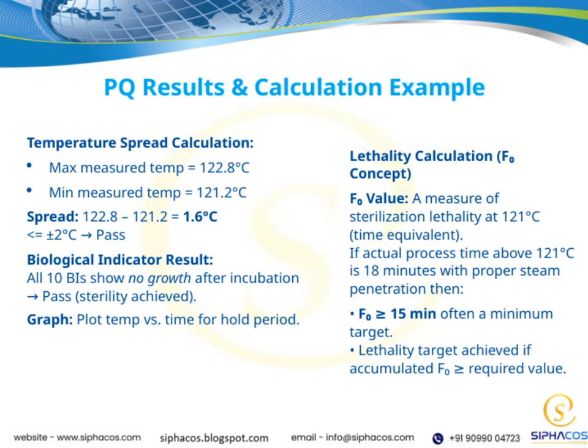Moving on to the PQ results and a calculation example, first, the temperature spread calculation. The maximum measured temperature was 122.8 degrees C, and the minimum was 121.2 degrees C, giving us a spread of 1.6 degrees C. Because this is within the acceptable range of plus or minus 2 degrees C, we pass this criterion.